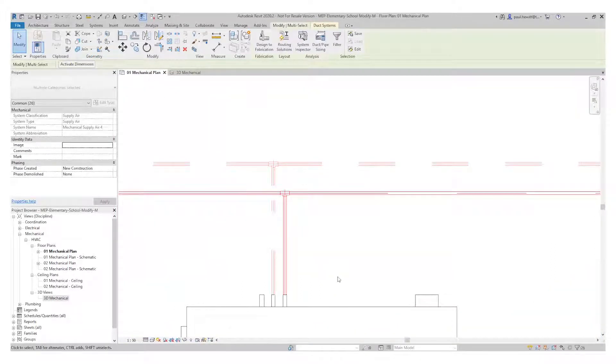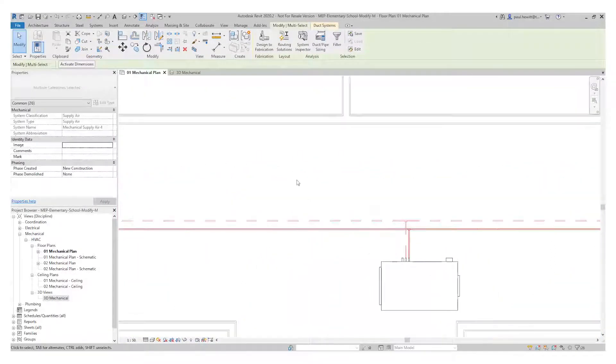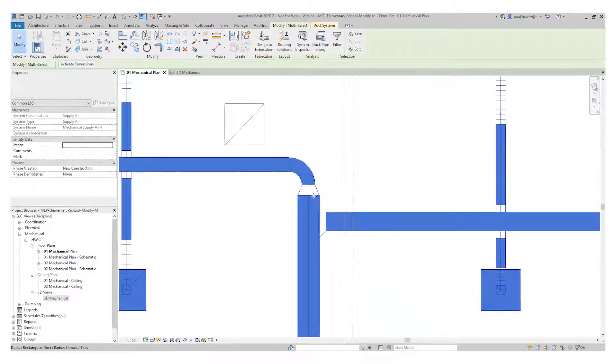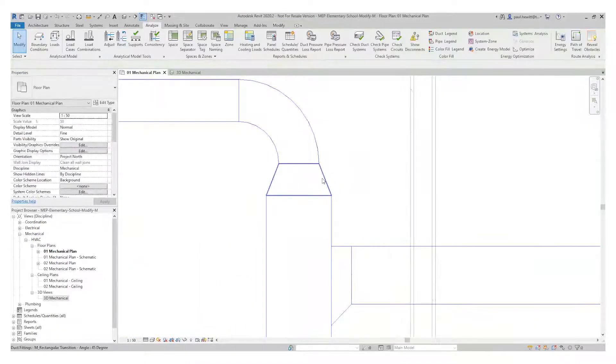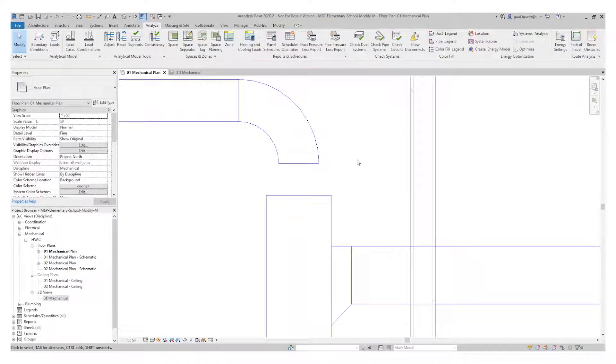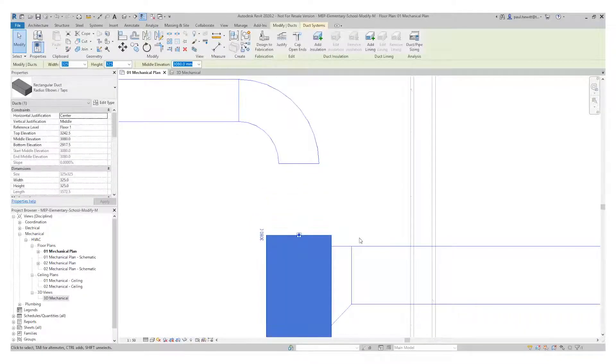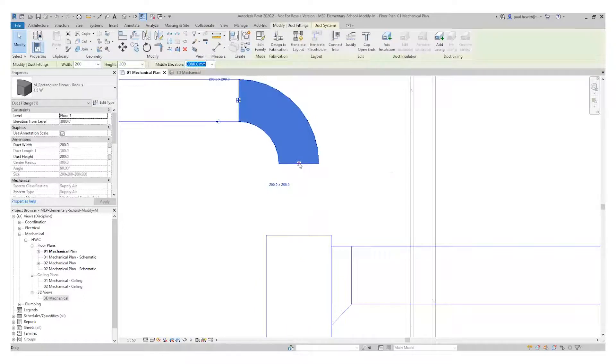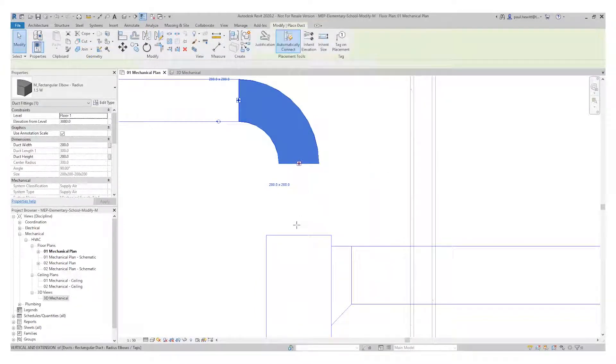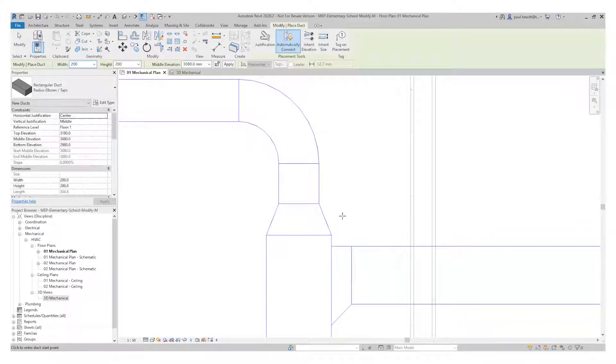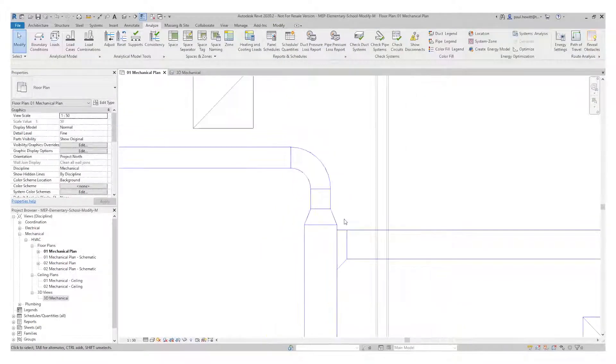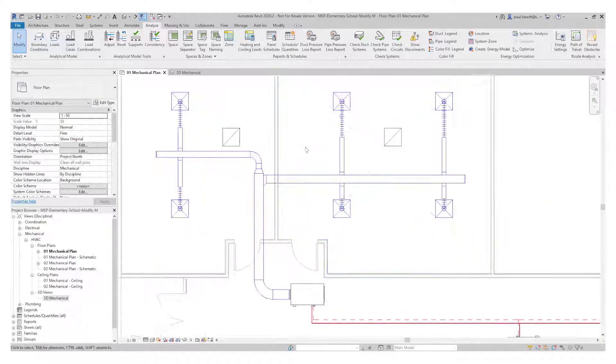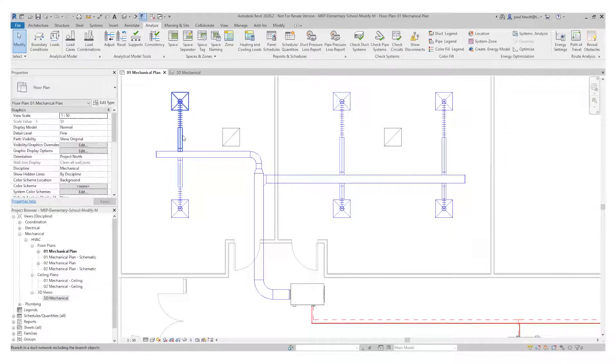So I'm going to switch to the mechanical plan view here and move to the duct. And I'm just going to modify this. I'm just going to remove that transition here, just really to move down this piece of duct, so we can actually remove part of the larger duct. Now in this case I'm going to right hand click on the bend and draw a duct. And I've done that this way because I want that sized duct as far down as possible. And it will put the transition in for me automatically. So there's my sized duct.